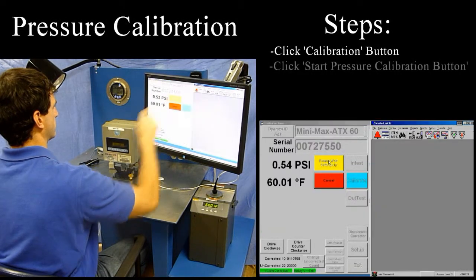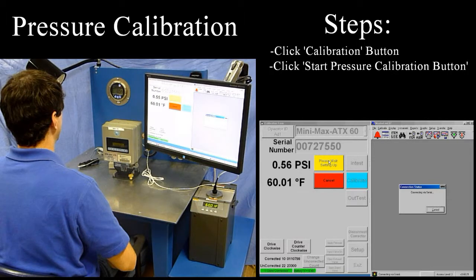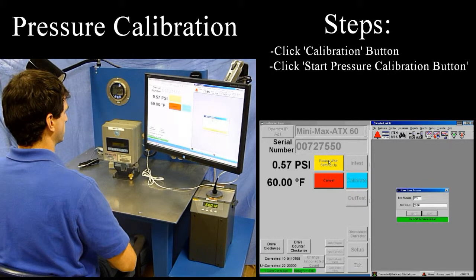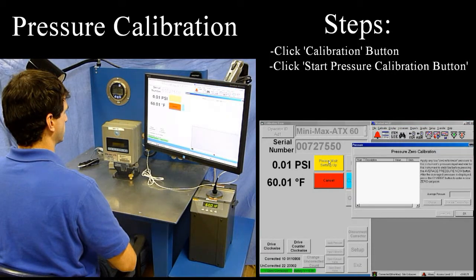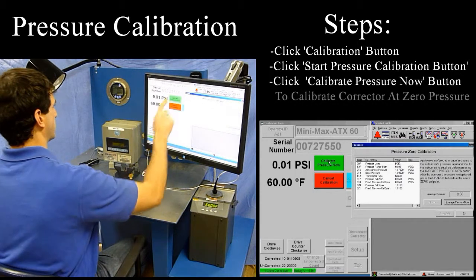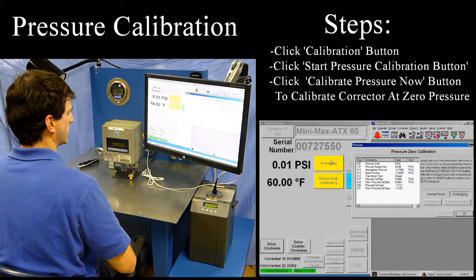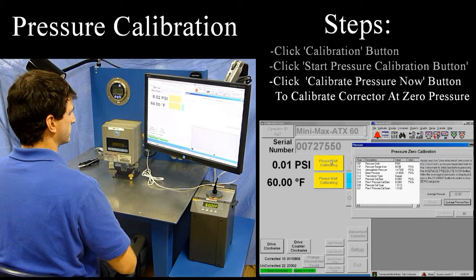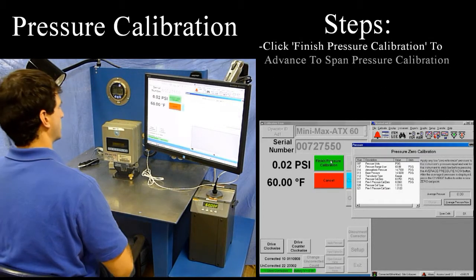The operator can calibrate the corrector by pressing the Calibrate button and selecting either pressure or temperature. When the Start Pressure Calibration button is selected, the software will initiate the pressure calibration sequence. If a 2-point calibration has been set in the setup menu, the stand will calibrate to the user-specified zero pressure and span pressure points. As with the in-test, the calibration process is advanced with the click of a button.